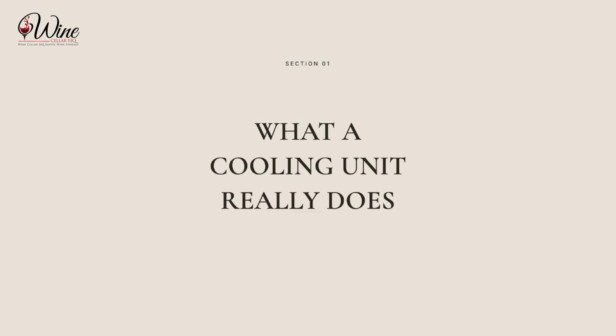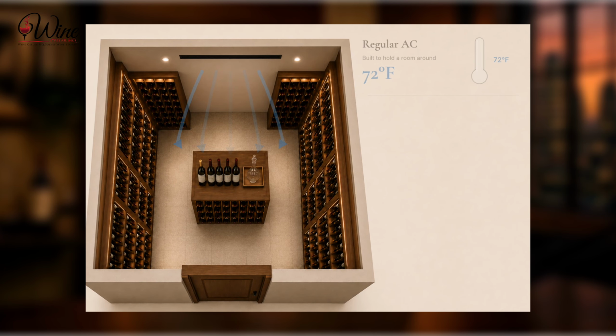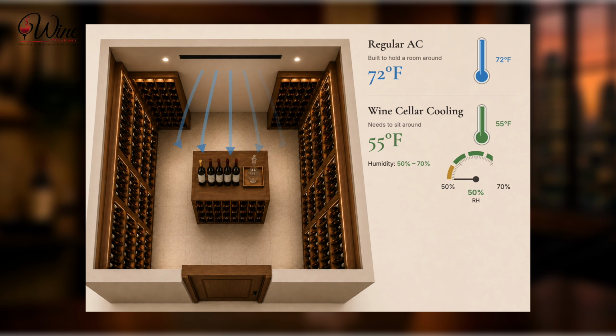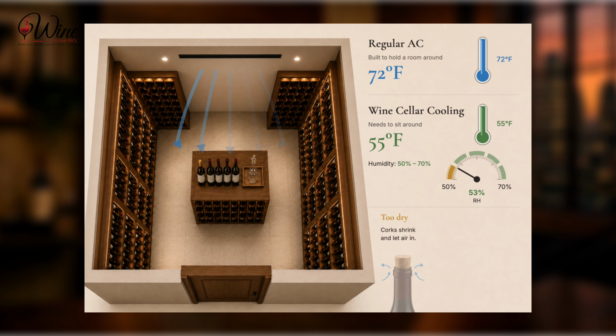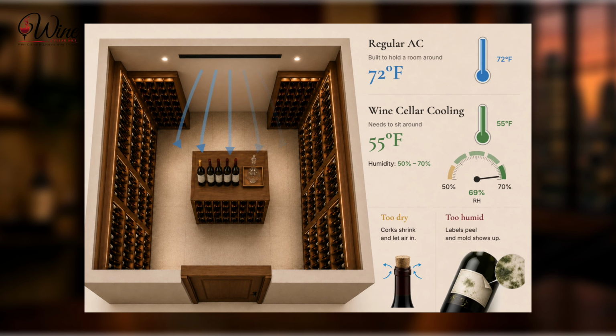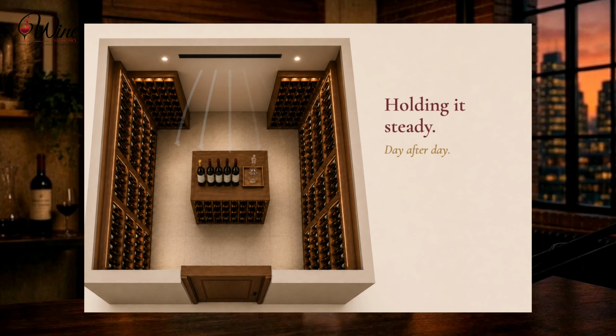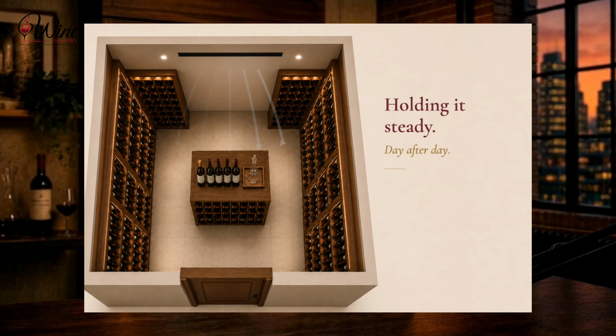First, the basics. A wine cellar cooling unit isn't just a small air conditioner. A regular AC is built to hold a room around 72 degrees Fahrenheit. Your wine cellar needs to sit around 55 degrees Fahrenheit, and it also has to hold humidity in a specific range, roughly 50 to 70%. Too dry and corks shrink and let air in. Too humid and labels peel and mold shows up. On top of that, it's not just about hitting that temperature once, it's about holding it steady day after day through summer heat and winter cold. That's a different, more demanding job than a standard air conditioner is designed for, which is why dedicated wine cellar cooling units exist in the first place.